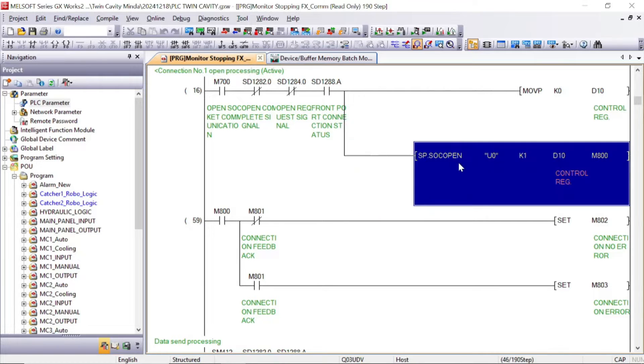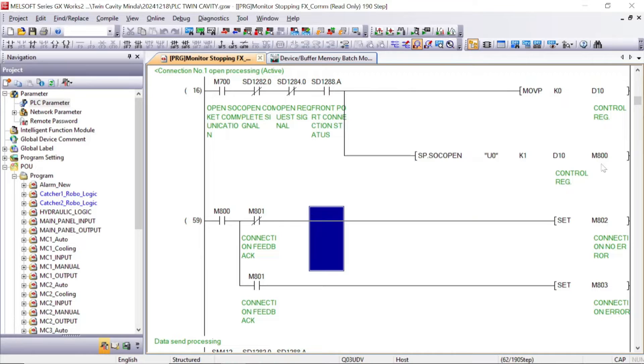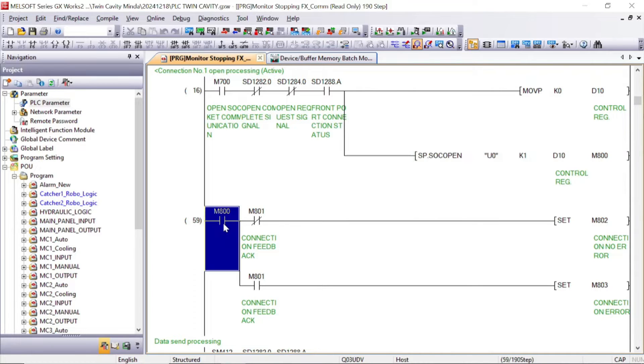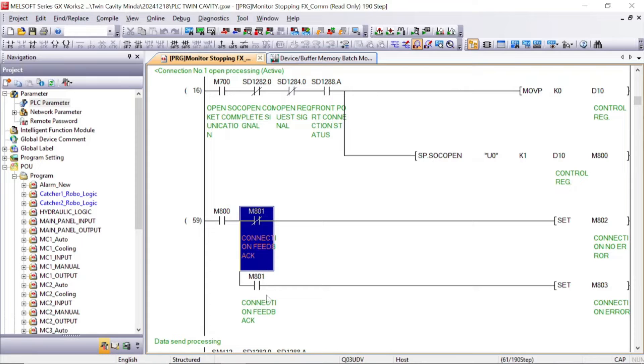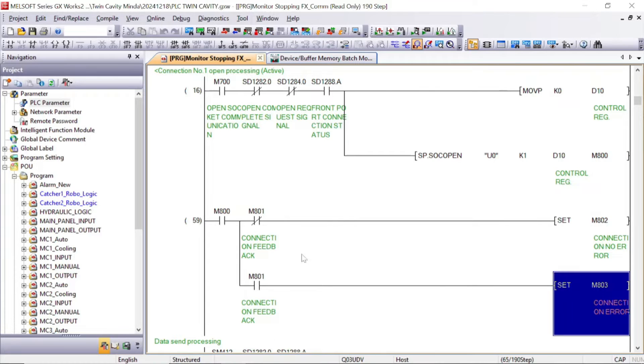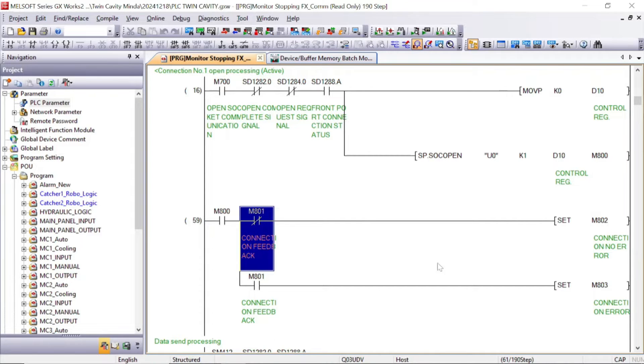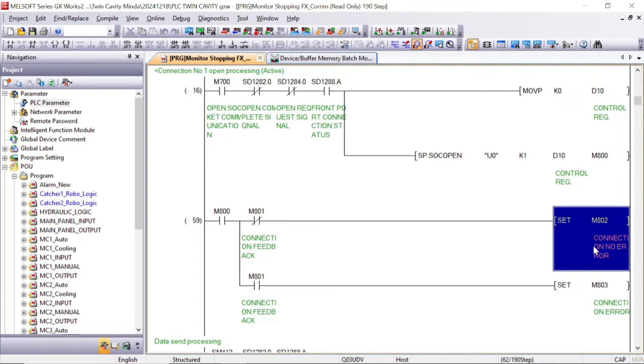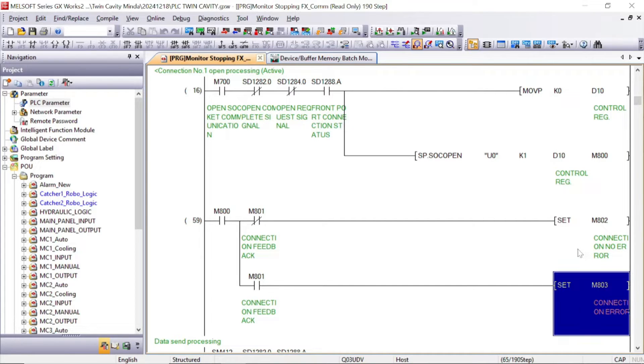For socket open communication, this is our connection number one, and D10 is for the control register. D10 and D11 — two registers will be used here. M800 will trigger, and M801 will give the feedback return. If this feedback is present there is a connection error; if M801 is off then there is no connection error. This bit will show us the communication error status.